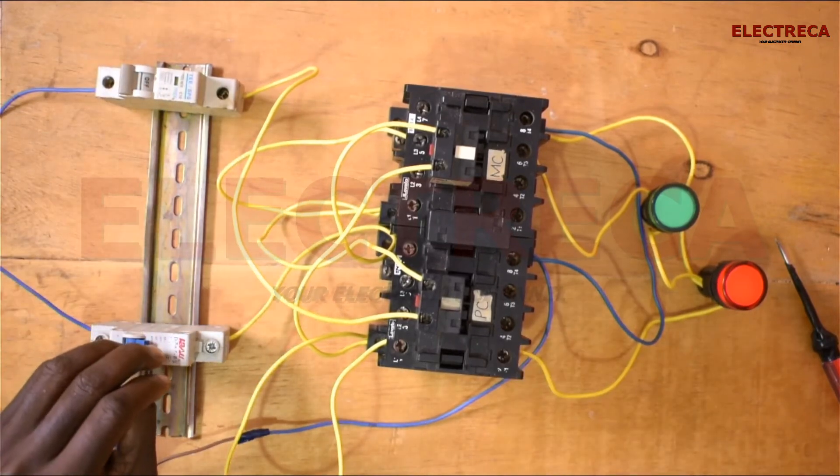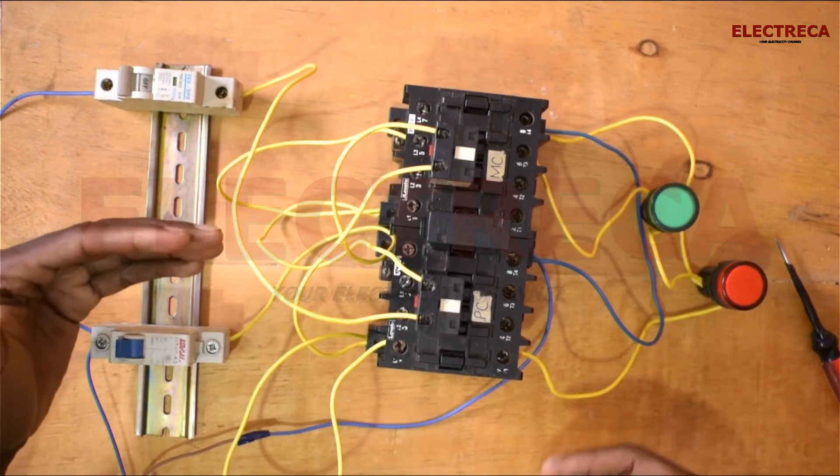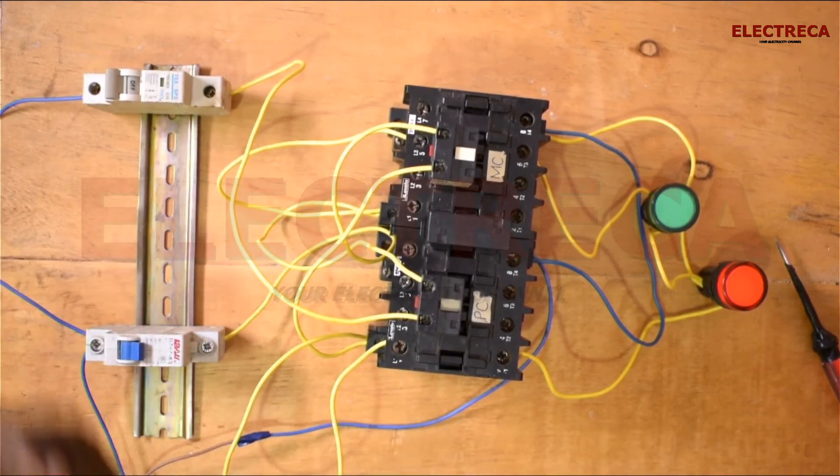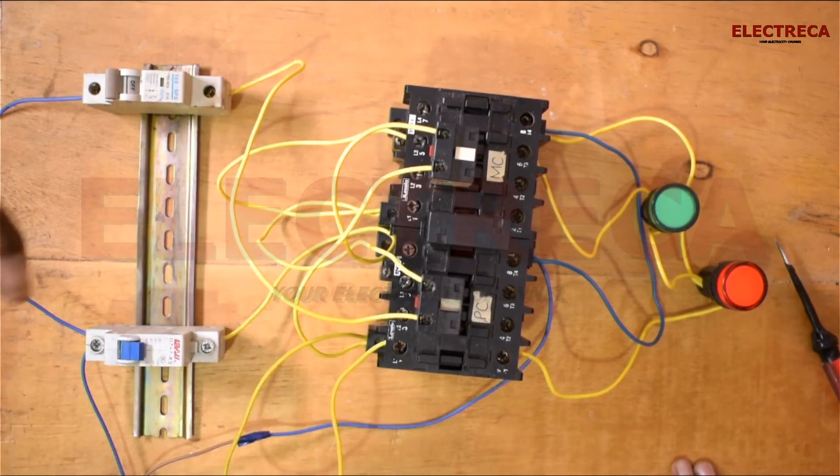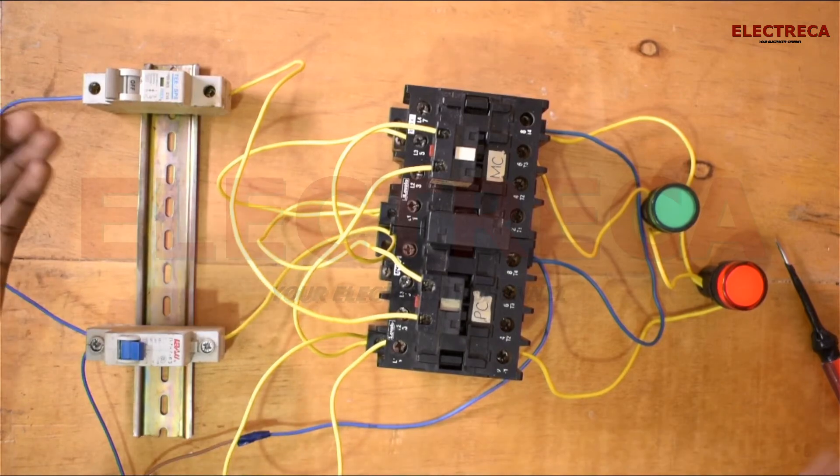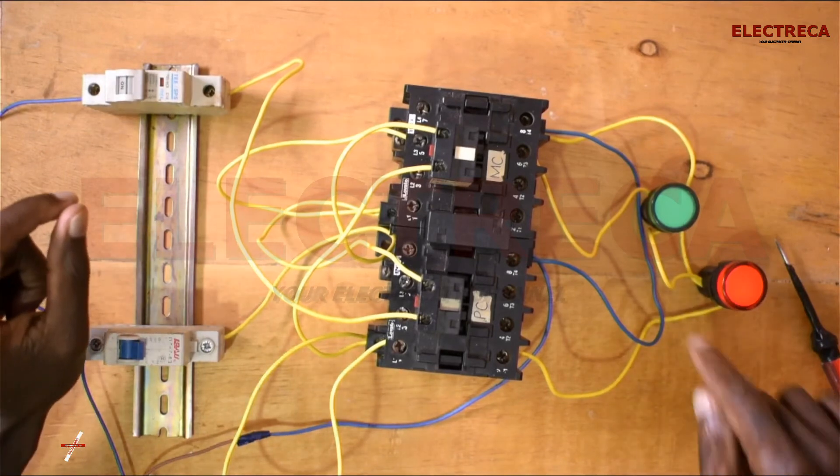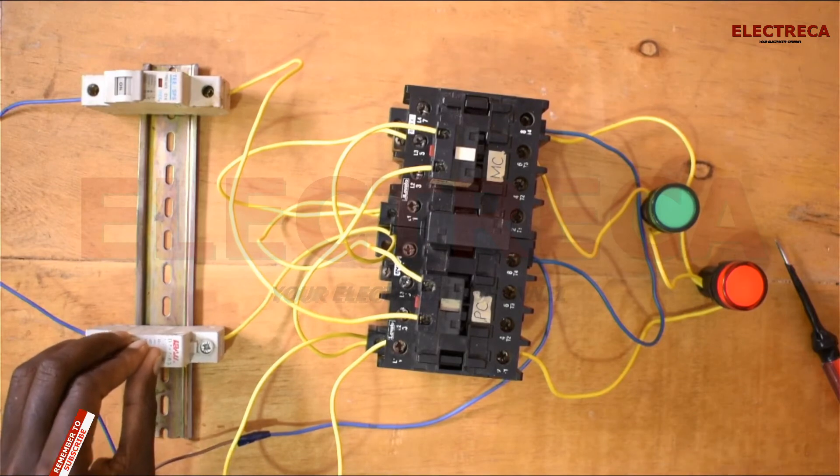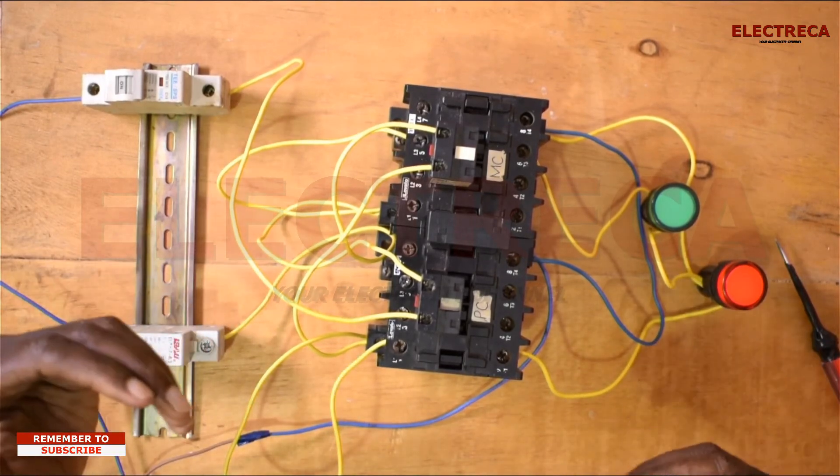So until you remove the main, that's when this will come in because you had already switched it on. This is really safe. If, for example, your backup was running the way this is now, and then maybe someone went and the utility power is back, it's back. You only have a light somewhere that will show you that it's back, but it won't be able to engage until you disengage the backup contactor.